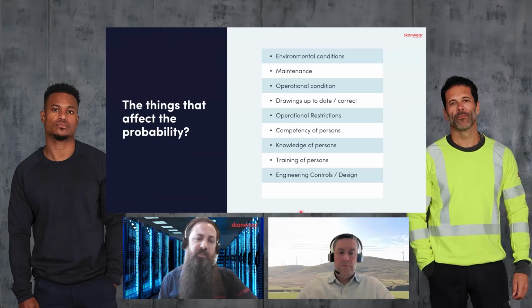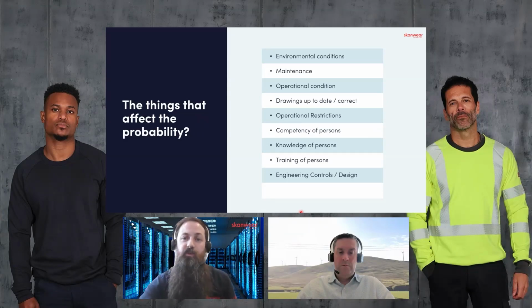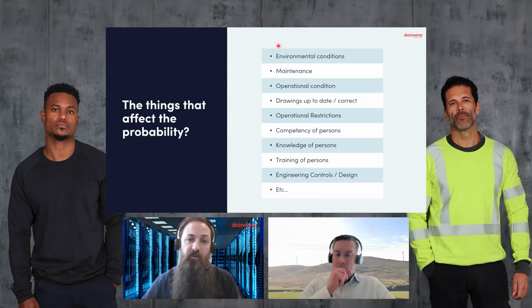Engineering controls or design also matter. Newer networks have many elements built in to protect people and reduce probability—whether older electromechanical relays or electronic relays, arc flash protection, or an arc-rated board that diverts the blast in the event of an arc. Maintenance switches, for example, reduce pickup time and incident energy. There are many such engineering controls and design features to keep people safe, and the list is non-exhaustive—there could be many others.